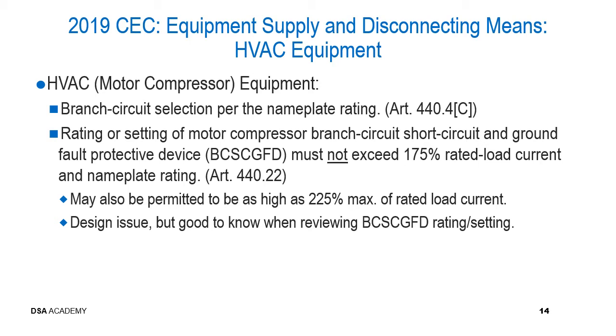The rating or the setting of the motor compressor, branch circuit, short circuit, and ground fault protective device, also abbreviated BCSCGFD, which is a lot of words and a lot of letters in an acronym, must not exceed 175% of the rated load current and the nameplate rating. That's identified in Article 440.22.